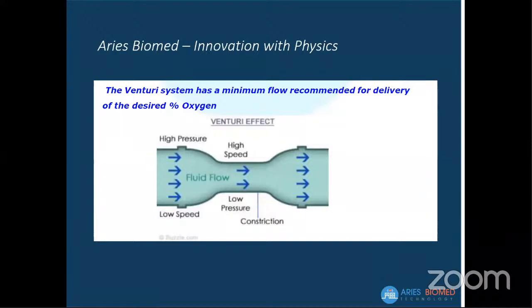2020 mid, we started an innovation on physics without using a turbine. We wanted to solve three problems. One is we don't want to use a power supply, because the turbine-based system requires import. The turbine needs to come from Korea or China, and we want to avoid that. The second thing is we don't want the device to be used with power, because if the device is to be used in an ambulatory setting, we don't want the ambulatory system to use power, right? And also to save oxygen.